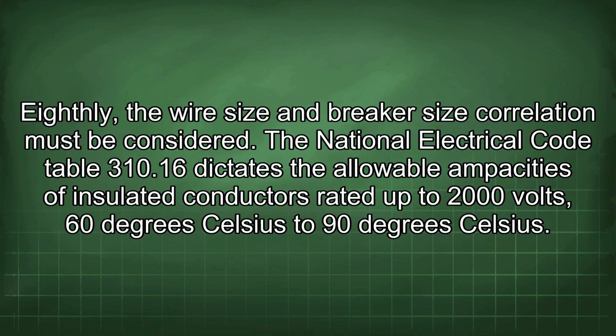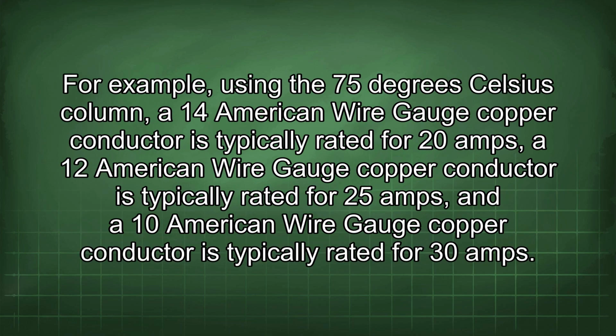Eighthly, the wire size and breaker size correlation must be considered. The National Electrical Code Table 310.16 dictates the allowable ampacities of insulated conductors rated up to 2000 volts, 60 degrees Celsius to 90 degrees Celsius. For example, using the 75 degrees Celsius column, a 14 American wire gauge copper conductor is typically rated for 20 amps, a 12 American wire gauge copper conductor is typically rated for 25 amps, and a 10 American wire gauge copper conductor is typically rated for 30 amps.